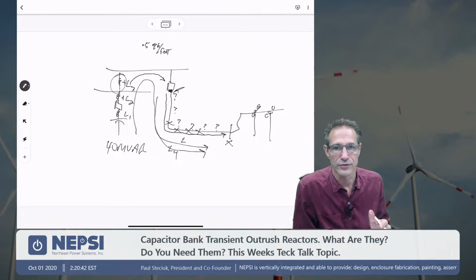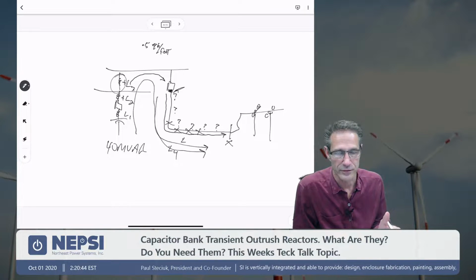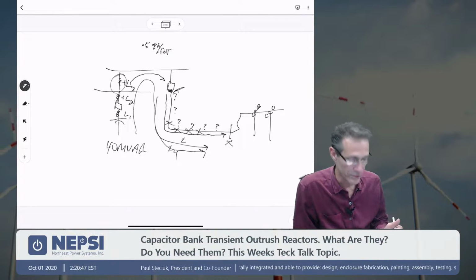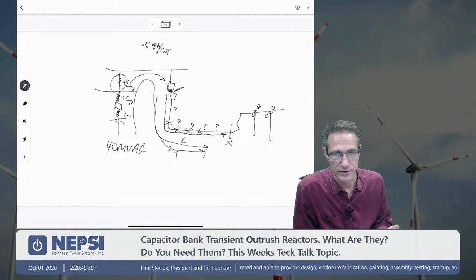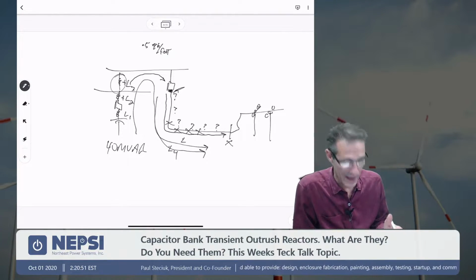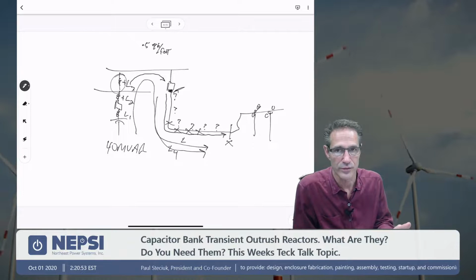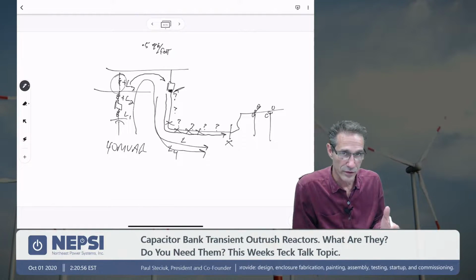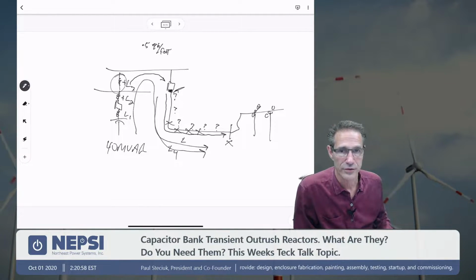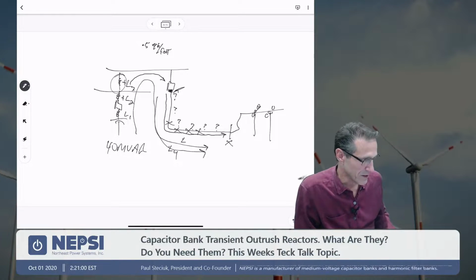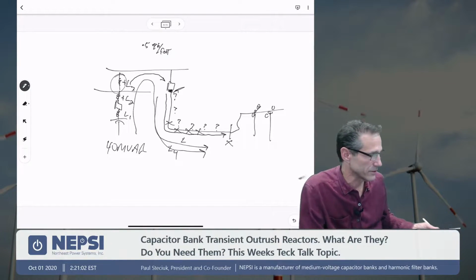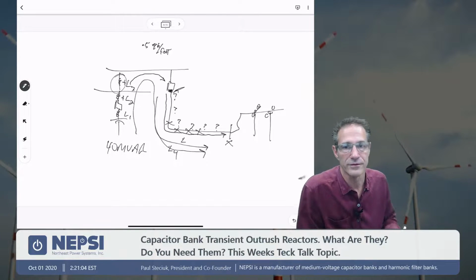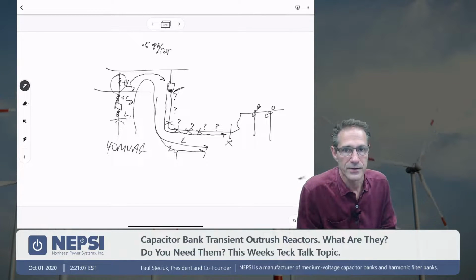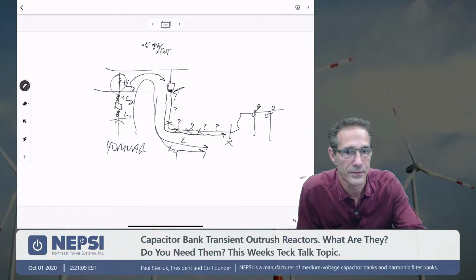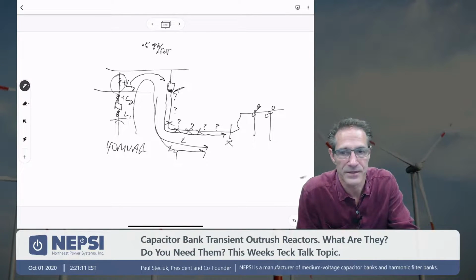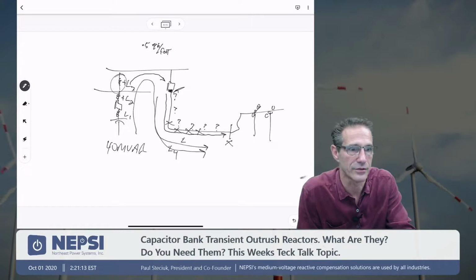most distribution faults are single phase to begin with. So you have another engineering decision to make: do I add this cost and dimension to my equipment for that? This is really all part of judgment when you're designing your system. But the type of fault in your capacitor bank connection is something to think about, and if you do, you may see that you don't need those outrush reactors.